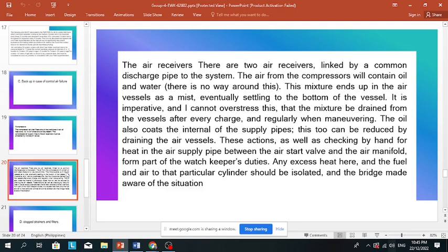It is imperative, and I cannot overstress this, that the mixture be drained from the vessels after every charge and regularly when maneuvering. The oil also coats the internal of the supply pipes. This too can be reduced by draining the air vessels. These actions, as well as checking by hand for heat in the air supply pipe between the air start valve and the air manifold, form part of the watchkeeper's duties. Any excess heat here and the fuel and air to that particular cylinder should be isolated and the bridge made aware of the situation.